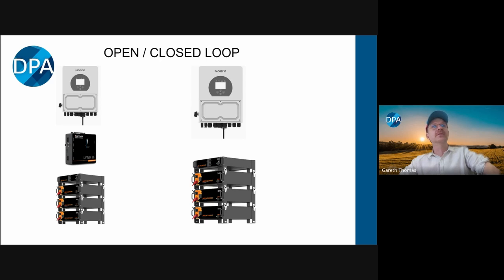Or you might want to do it because the inverter doesn't have comms, it's an older system. We had one with an older SMA recently where the comms were only designed for NMC batteries. So we ran an open loop scenario. Or if you're just not comfortable with that sort of thing, you prefer something like Power Plus, Discover is exactly the same. You can just run it open loop. Even if you're doing that, you could still install the Link 2 anyway and not have it connected to the inverter, so that you could have the online monitoring of the battery bank if you wanted to, and you can come and get the downloads of all the history data.